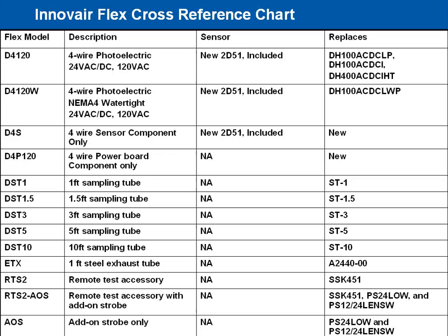Like I said, these guys do replace the old System Sensor product line. So on the left side is the new Flex model numbers. So D4120 is your everyday workhorse. D4120W is your watertight version. Here's your sampling tubes down here. DST5, a 5-foot sampling tube, would be your most common.